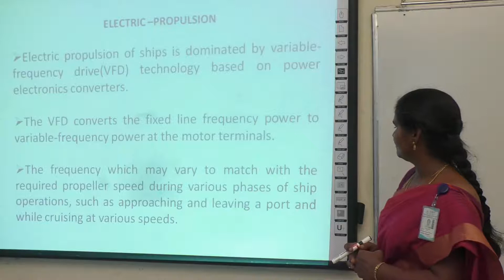These power electronic converters are mainly used to control the speed of the motor and the speed of the propeller. The VFD converts the fixed line frequency power to variable frequency power at the motor terminals. The frequency may vary to match the required propeller speed during various phases of ship operations, such as approaching and leaving a port and while cruising at various speeds.